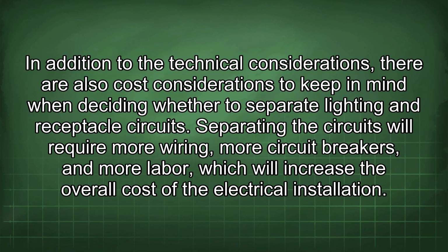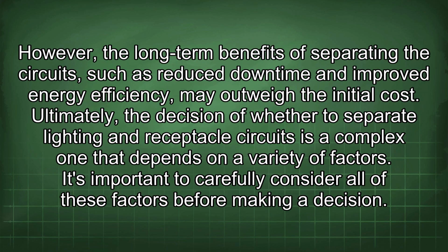In addition to the technical considerations, there are also cost considerations to keep in mind when deciding whether to separate lighting and receptacle circuits. Separating the circuits will require more wiring, more circuit breakers, and more labor, which will increase the overall cost of the electrical installation. However, the long-term benefits of separating the circuits, such as reduced downtime and improved energy efficiency, may outweigh the initial cost. Ultimately, the decision of whether to separate lighting and receptacle circuits is a complex one that depends on a variety of factors. It's important to carefully consider all of these factors before making a decision.